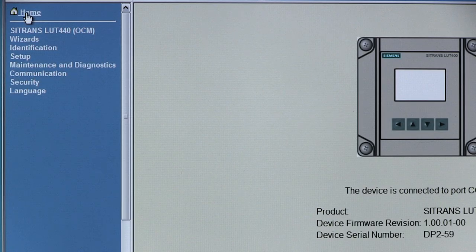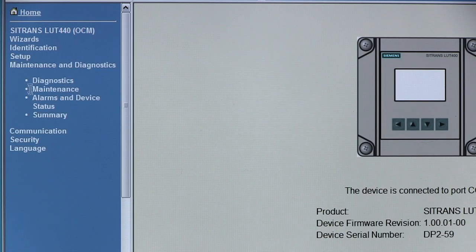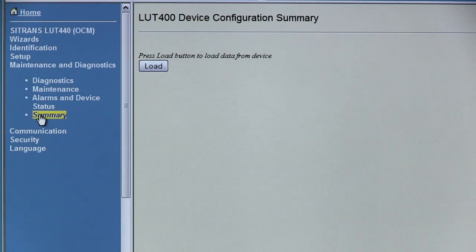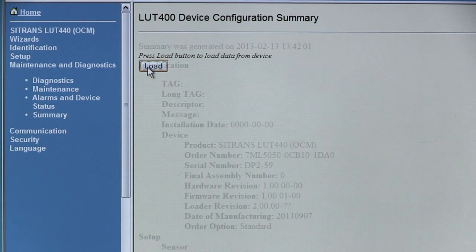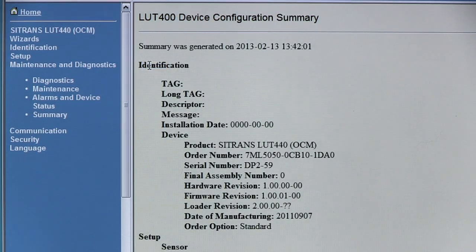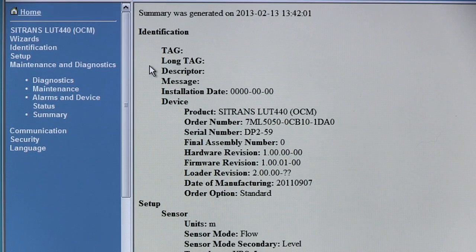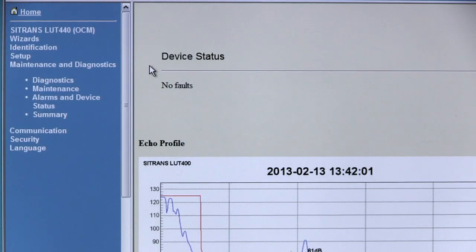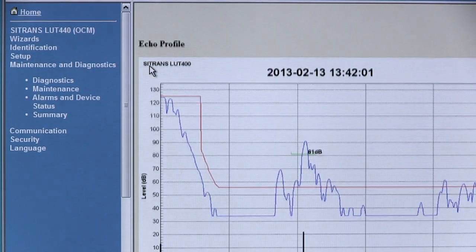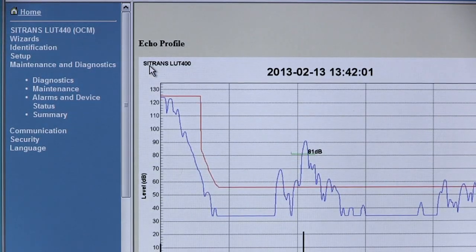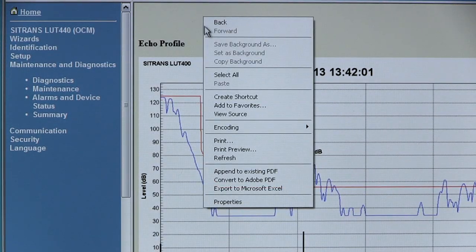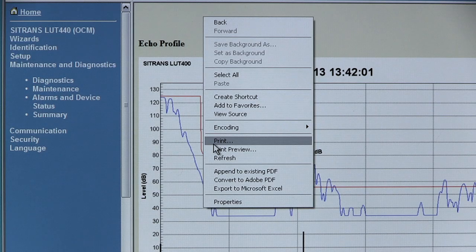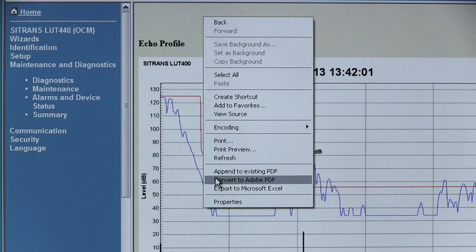With the browser tool you can create a configuration summary for your records. Click on the summary menu item, then click the load button. The full parameter list and an echo profile are transferred to the browser tool. Right-click in the window to print the parameter list or to save the list as a PDF file.